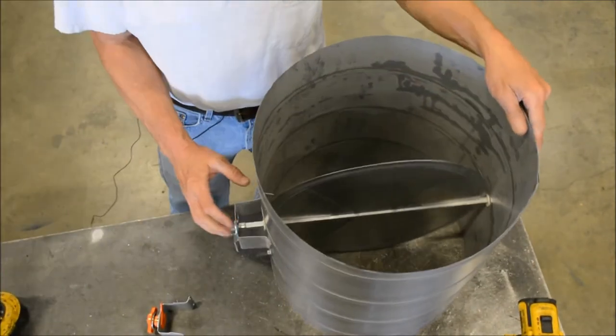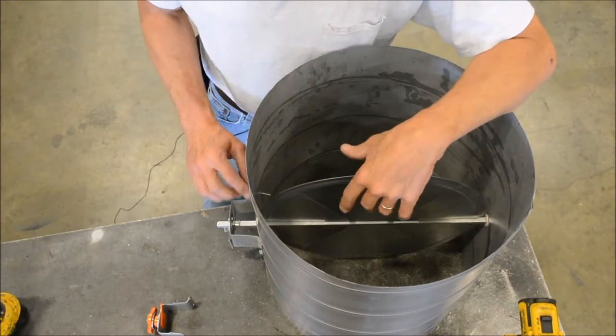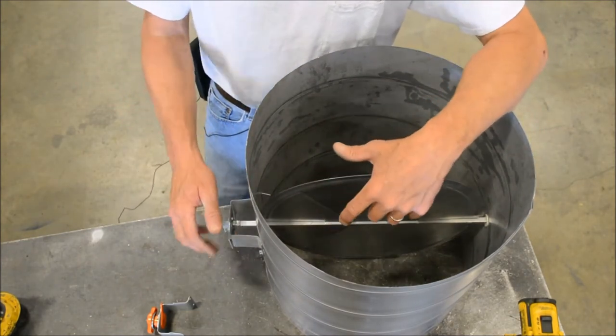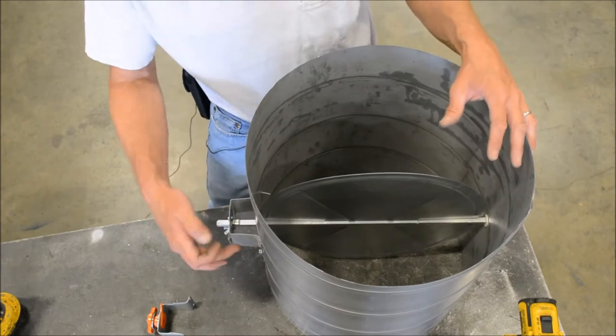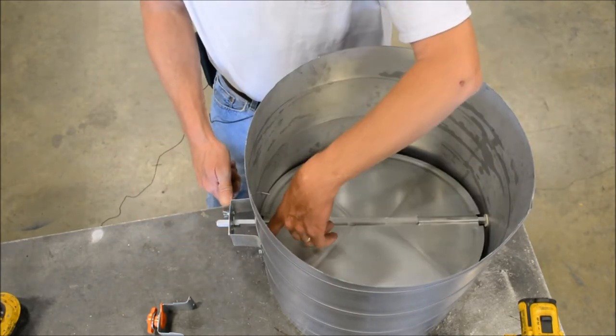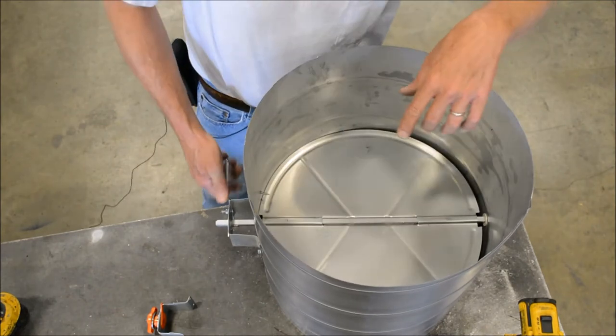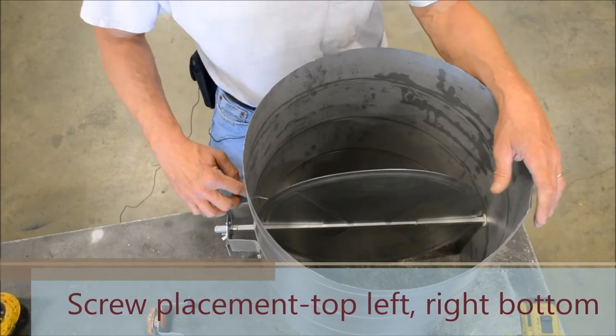Okay, why we did that was because whenever the blade closes, if you have the screws here and here, your handle turns, your screw hits. So we install them at the opposite corner, or with the blade open that'll be to the left top, right bottom.